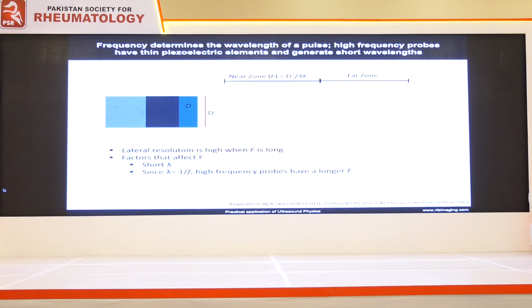So what's important here? The important thing is that the near zone, which is the bit where you have the best image, is inversely proportional to the wavelength. Your frequency is inversely related to the wavelength. So a high frequency probe will produce short wavelengths, and short wavelengths will allow you to have a larger near zone. And that's what we want, a nice, good near zone. So the higher frequency probe you have, the better resolution you will have, because most of your image will be coming from the near zone. The downside is that with short wavelengths, the penetration through the tissue is very poor. Therefore, if you use the high frequency probe for a deep structure, the sound waves just don't make it because they're too short. So the key thing is to find the right probe for the right job. We'll go through that in a minute.